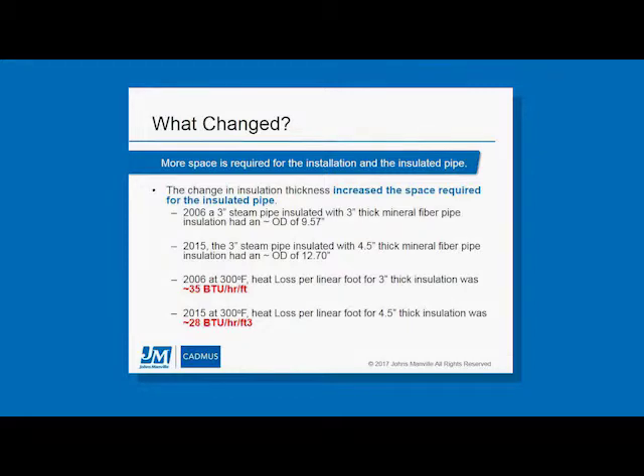Going down the bullet items, in 2006, a 3-inch steam pipe, which was required to be insulated with 3-inch thick material, had an insulated outer diameter of just over 9.5 inches. By 2015, this increased to 4.5-inch thick insulation, increasing the outer diameter of the insulated pipe to 12.7 inches for this example. So there was an increase of 3 inches in diameter required for the space for that insulated pipe. And if you recall the photo of the plenum space that has the mechanical distribution systems running through it, a lot of times that space is not planned for and it can be a real issue. The 2 bottom bullet points show that there's about a 20% savings in heat loss with that change in insulation thickness from 2006 to 2015.